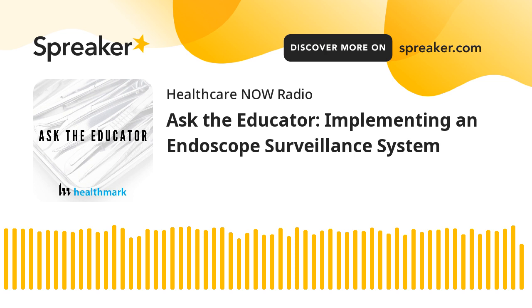But TFF is turbulent fluid flow. And this is an enclosed system. So there's a box much like the size of an endoscope drying unit that we're used to seeing. In fact, this unit does have drying capabilities too, as an added benefit. But it is an enclosed system that you hook up sterile water to in a syringe, and it flushes air into that water at a specific rate that's then injected into the endoscope, and it creates that shearing effect, or that contact with the lining of the channel itself, where we don't typically get a lot of flow when taking samples. So it's an enclosed system.